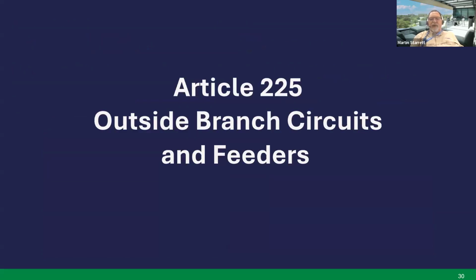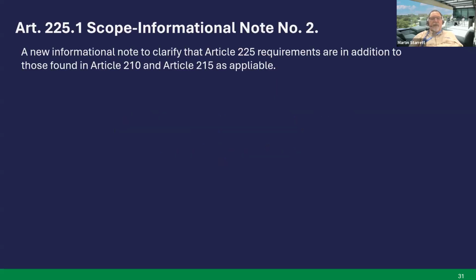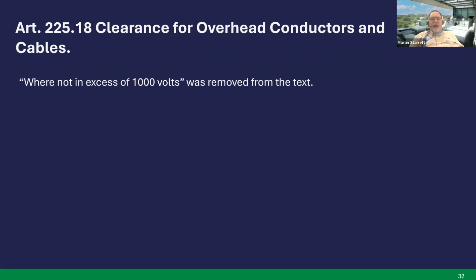Article 225, outside branch circuits and feeders. So the scope in 225.1, there's a new informational note, number 2. This note clarifies that Article 225 requirements are in addition to those found in Article 210 branch circuits and Article 215 feeders as applicable. So you got to meet the requirements in those two articles, but the ones in 225 are in addition to those.